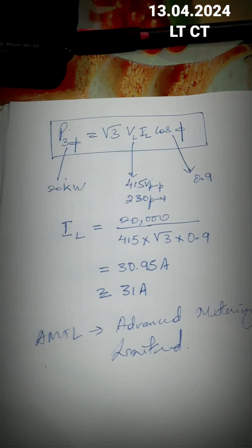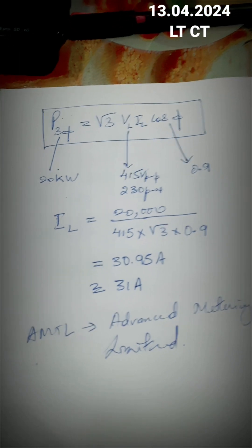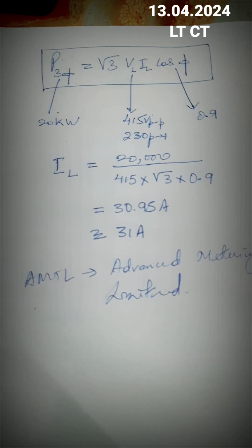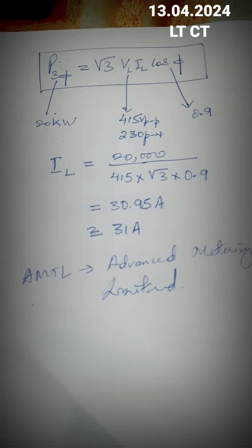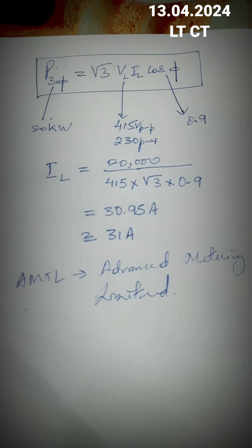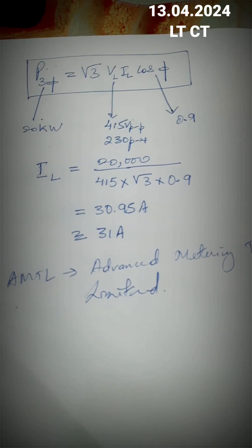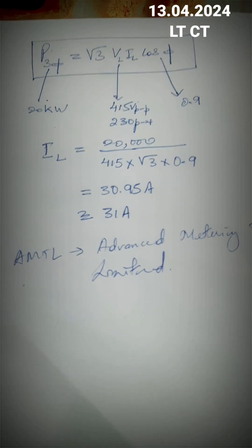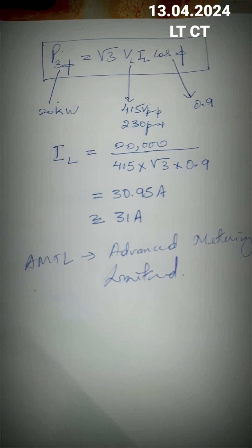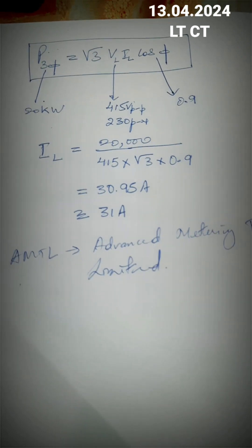Before we open this CT, let's do a calculation. This CT is used for connected loads of 15 to 22 or 23 kilowatt. The three-phase power formula is: P = √3 × VL × IL × cosφ, or equivalently 3 × Vphase × Iphase × cosφ. Taking VL as 415 volt and power factor as 0.9, the line current works out to 31 ampere. So we need a CT rated higher than 31A — that is a 50 ampere primary rating — giving us the 50 by 5 CT ratio.